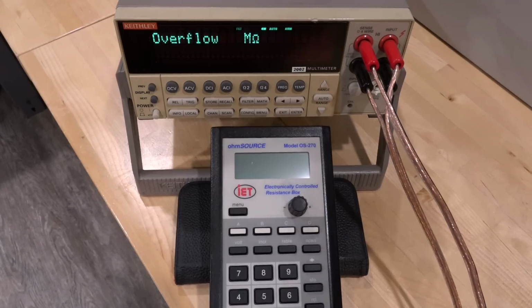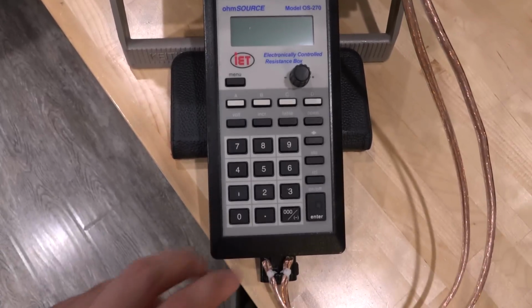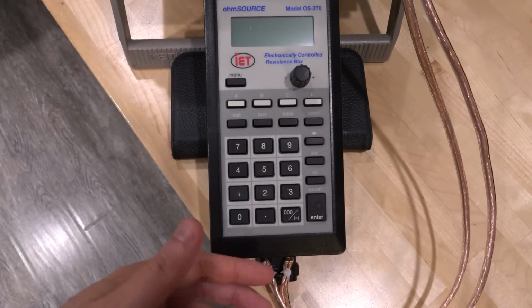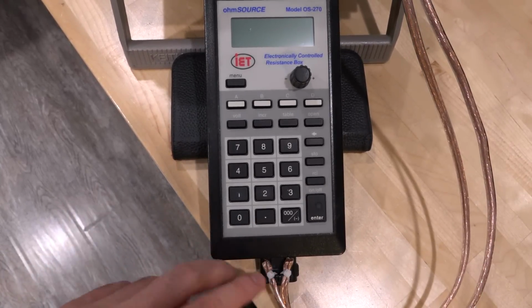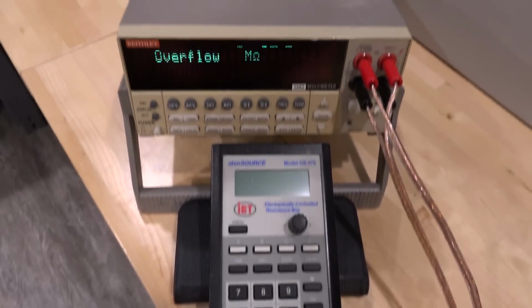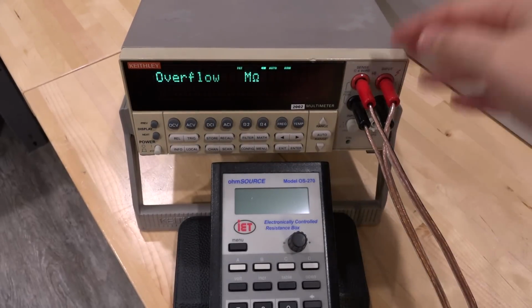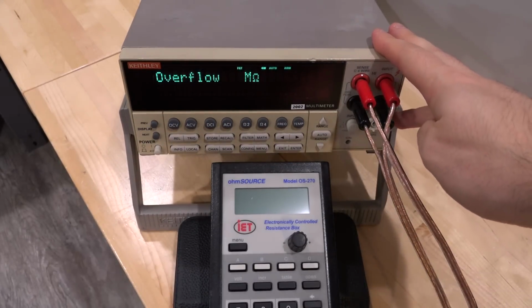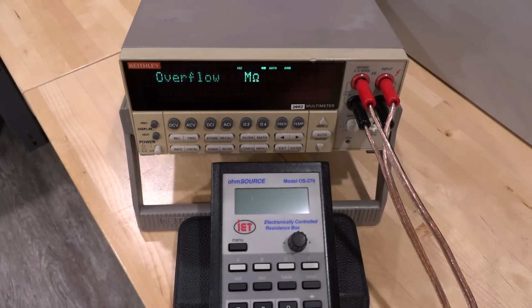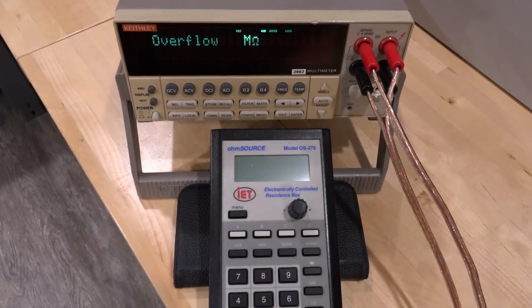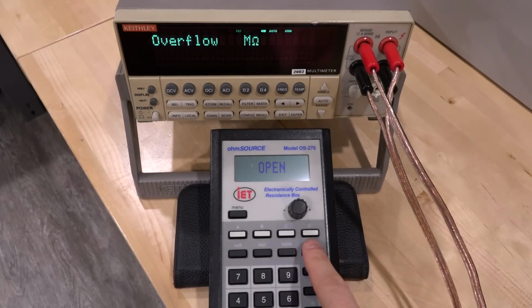The instrument itself doesn't have a Kelvin connection. It only has a banana plug in the front. So I have created a simple Kelvin connector by bringing two wires to each of these and then being able to do four wire measurement. This is a Keithley 2002. It's an 8.5-digit multimeter, so we should have no problem calibrating and measuring it. So right now, if I turn this on, we are in open. So let's try something like that.